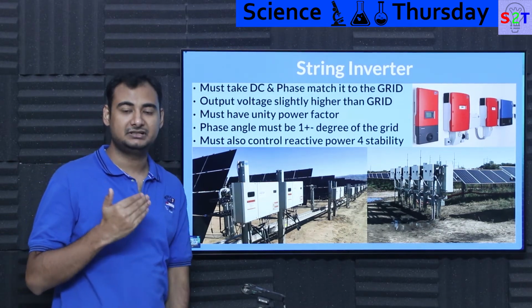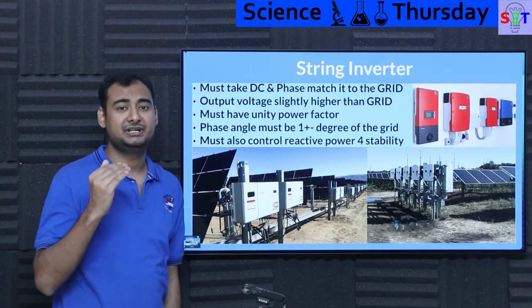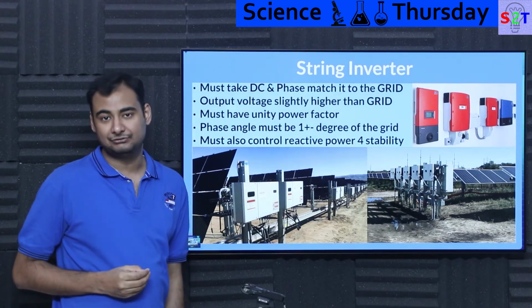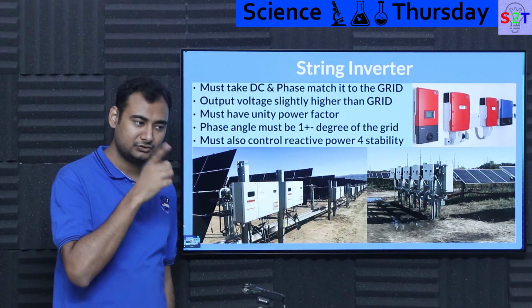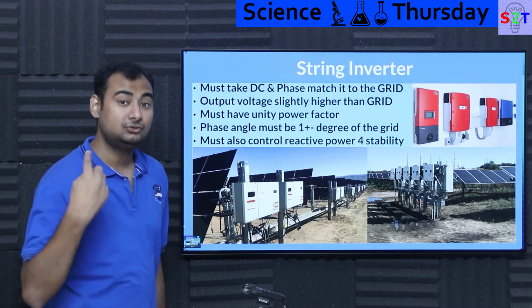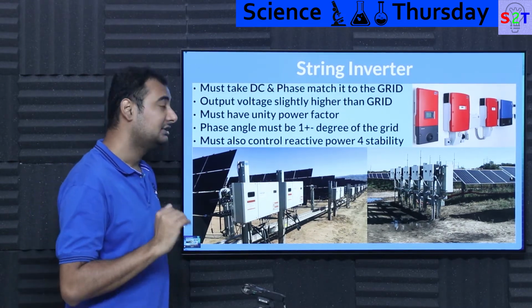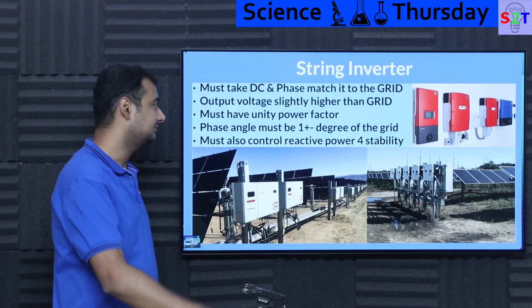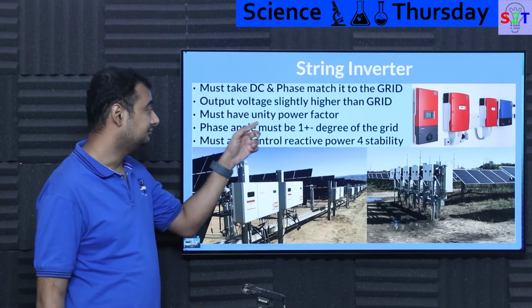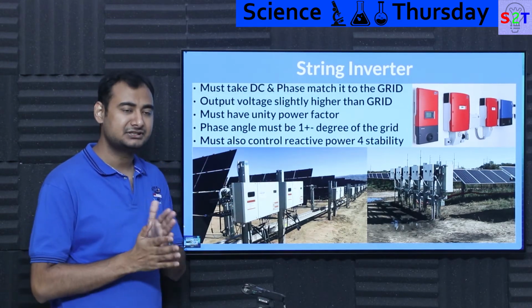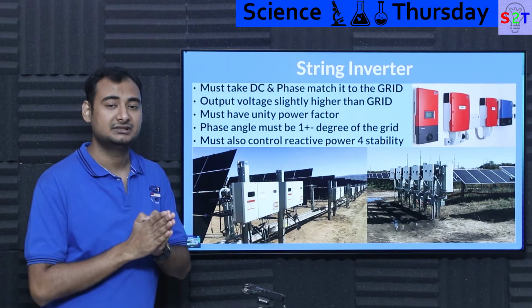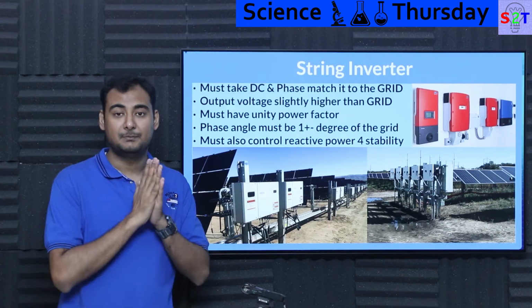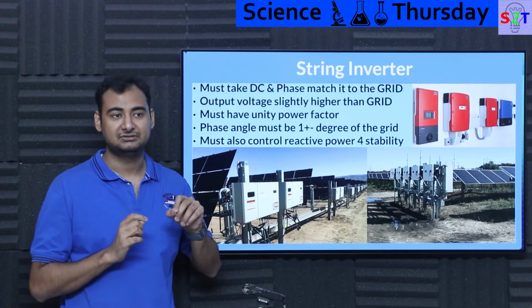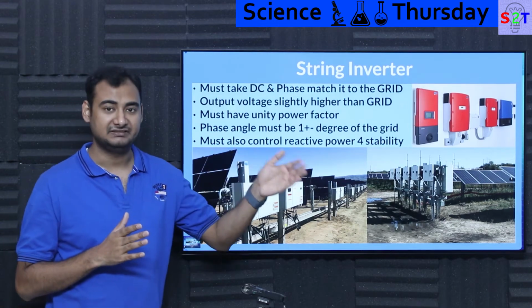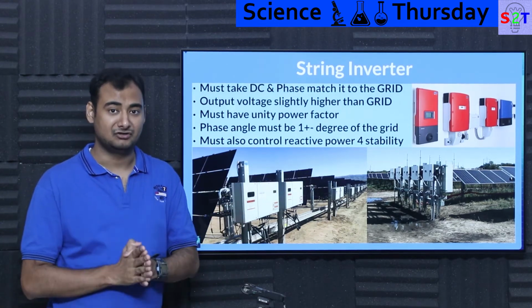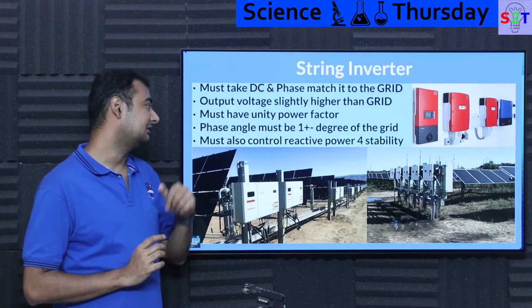And generally what grid tie does is they will raise their voltage a bit. So let's say I'm receiving 220 volts, my grid tie inverter will sell it at 222 volts, 2 volts higher. So that will allow us to pump energy into the system. Now it must have what we call unity power factor. What does that translate to? That simply translates to a scenario where the voltage and current must be in sync. Basically there cannot be leading or lagging, it must be one on one. So it requires unity power factor.